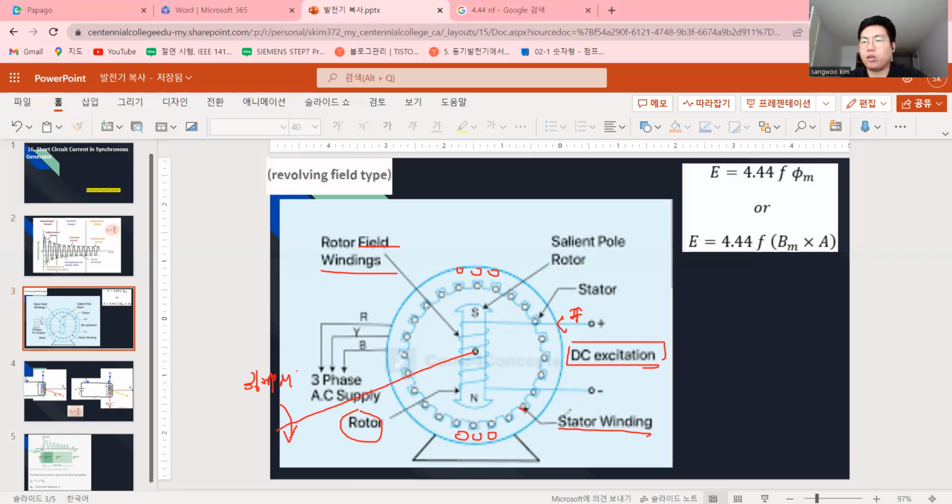So the damper works as a brake or as an axial rotation, to match the speed to be the same. And a synchronous motor doesn't have a start torque. That's why the damper winding also works as an induction motor winding. Yeah, this is a basic concept.